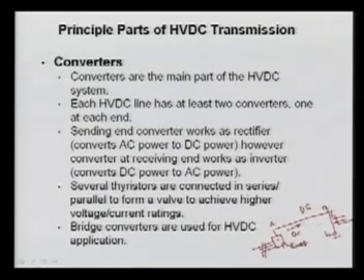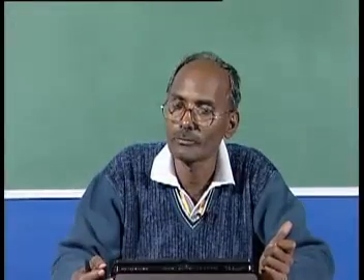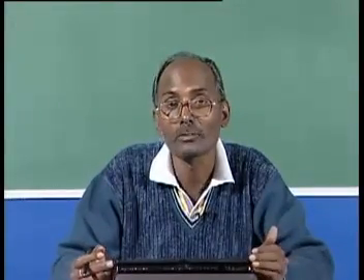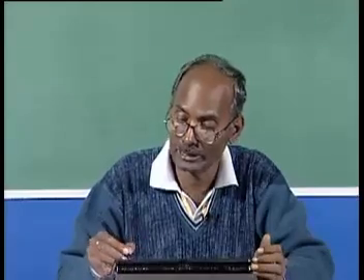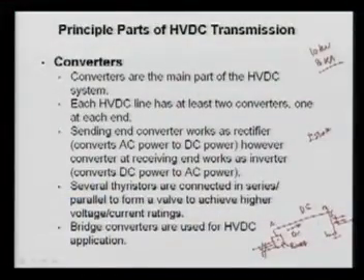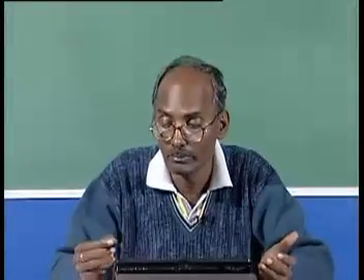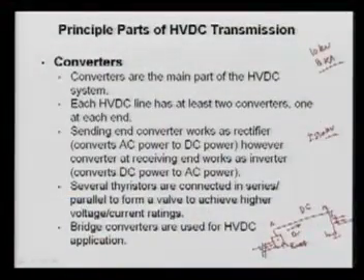This is called inverter operation. Now we know that, in the FACTS devices, when I was talking about the various devices, I said that we are having one single thyristor unit of 8 kilovolt that we are expecting, with a kiloampere rating. But I said an HVDC link here, let's suppose plus minus 500 kV, so current may be in the kiloamperes, even several mega amperes. So what we normally do is go for the addition of thyristors. We have to add in series to provide the proper voltage level, and also go for the parallel combination to provide the complete current rating of the link.